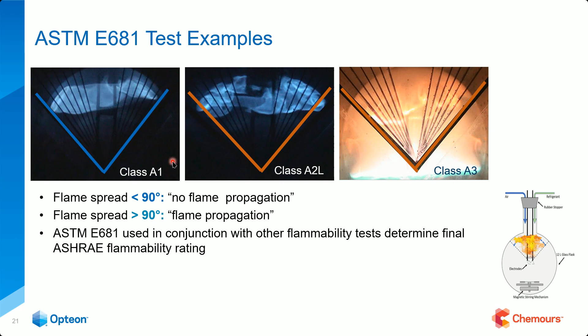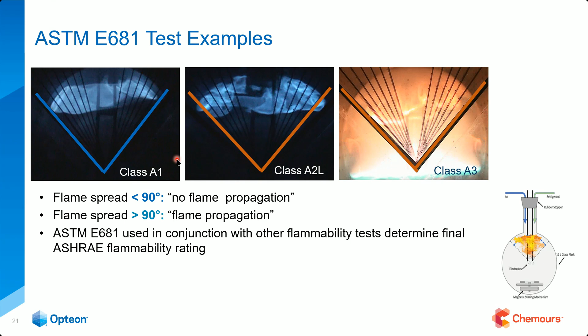This classification is brand new to the US and fairly new to the face of the earth. Again, the first letter is your toxicity, and the number is the flammability. The higher the number, the higher the flammability. A just stands for low or no toxicity. I like to say low because anything with enough parts per million will asphyxiate you.